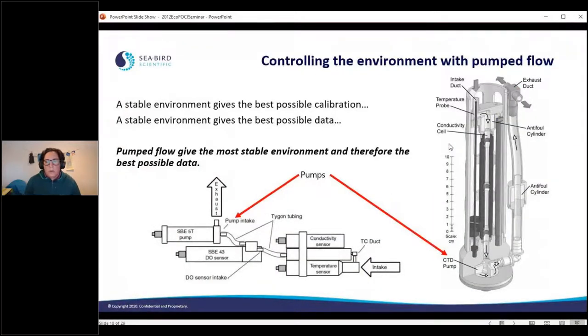And then the last thing is, I think one of our biggest things we like to do is really controlling the environment that the sensors are going to go into. The ocean is wild, there's lots of changes. One of the things we really bring to the table is that, I guess I'm just a convert at this point, but really pump flow is the best way to give you your best data. The reason why is because you're controlling the environment past your sensor. So a stable environment will give you the best possible calibration and the best possible data, but that's not always possible because you're just in the ocean, right? You're throwing stuff in, there's waves, there's changes in temperature. Pumped flow for us gives the most stable environment and therefore the best possible data, which is why so many of our sensors are pumped. Because if you want to get into that high accuracy and not have to make lots of corrections, that's the best way to do it.